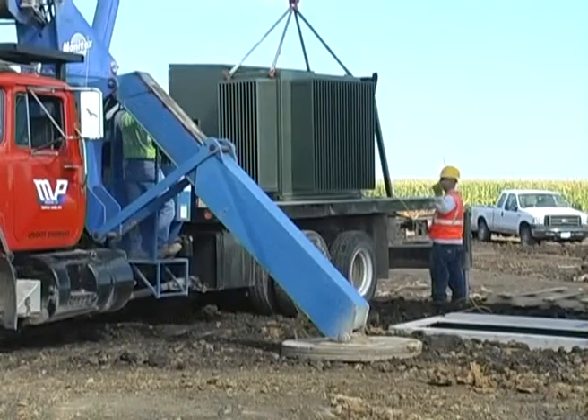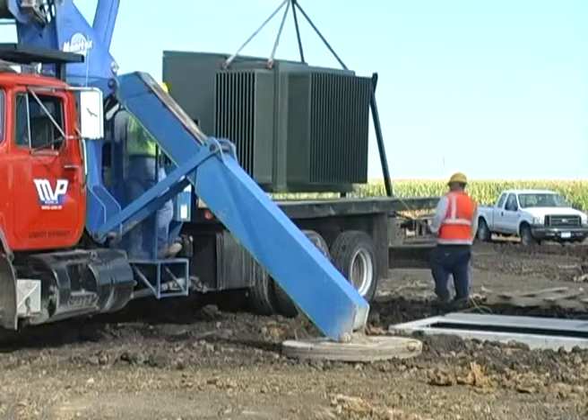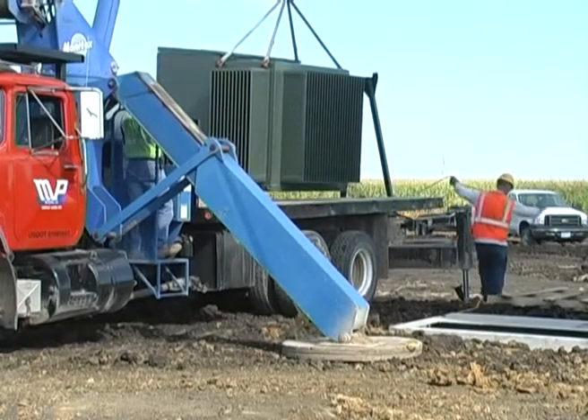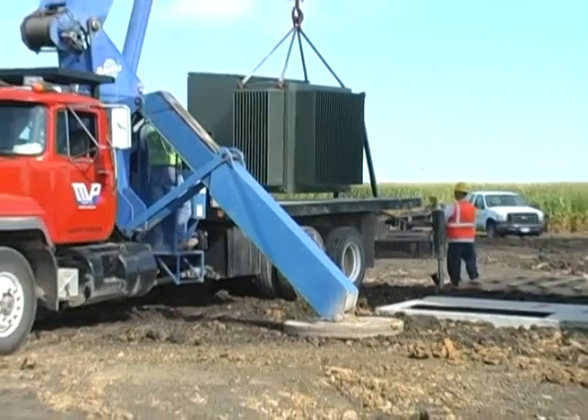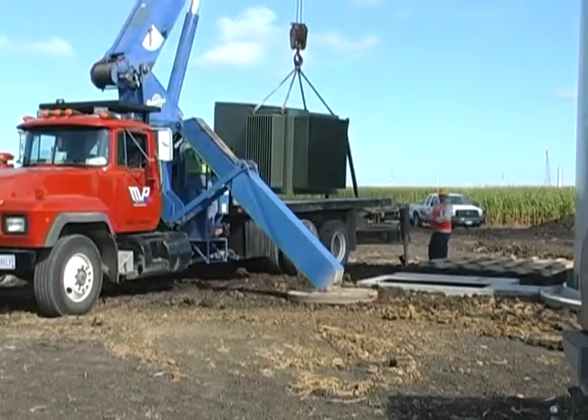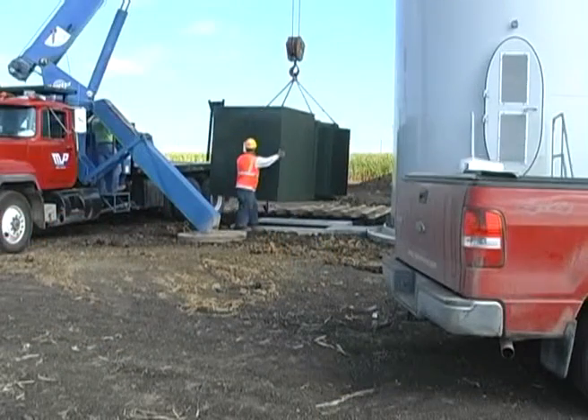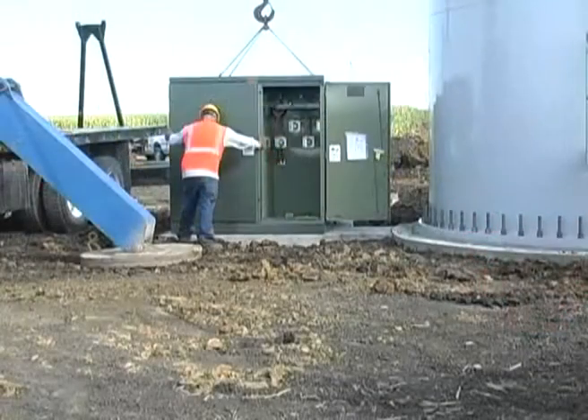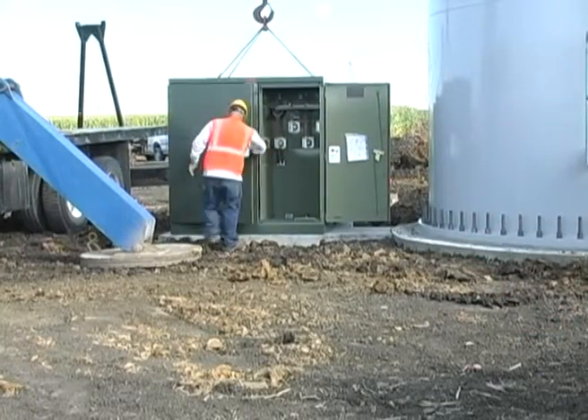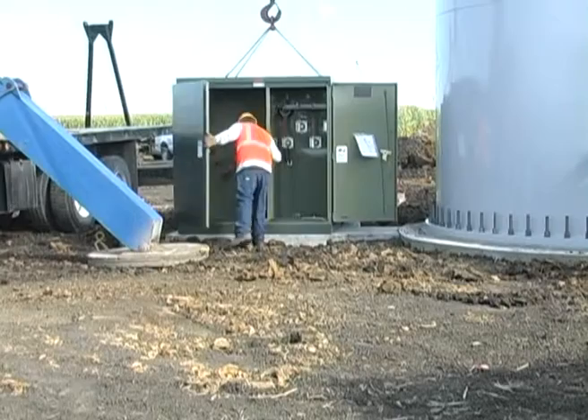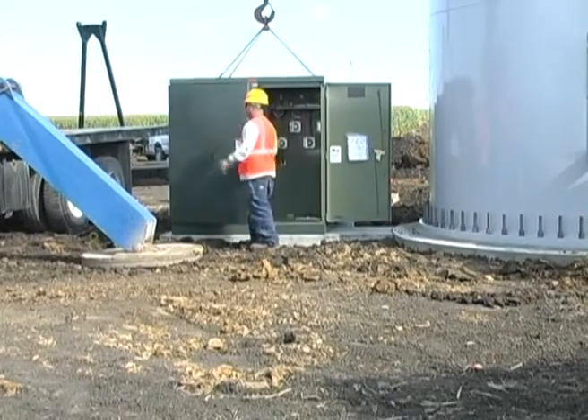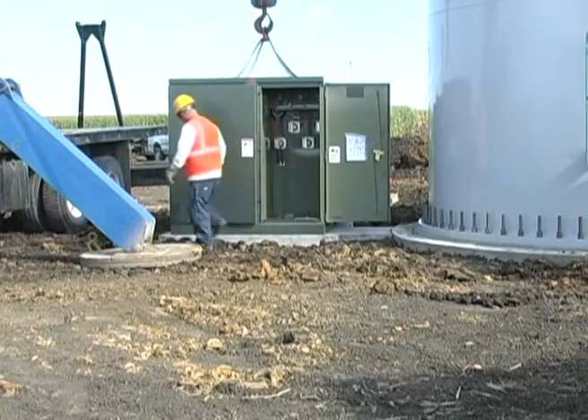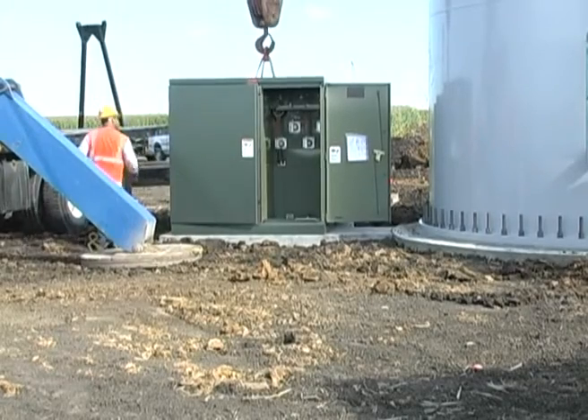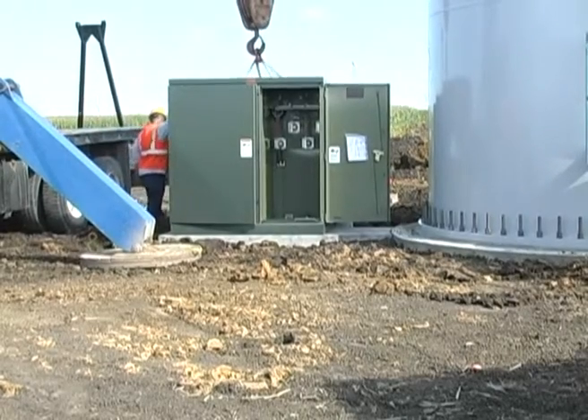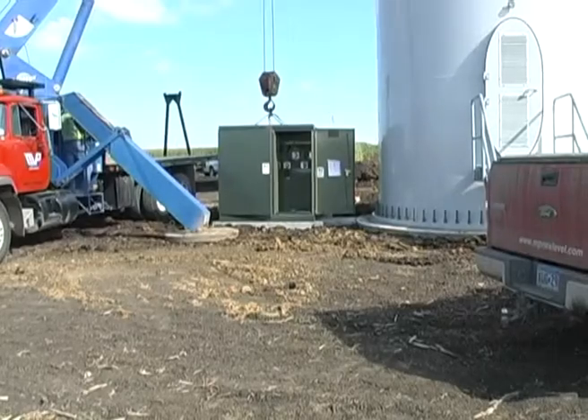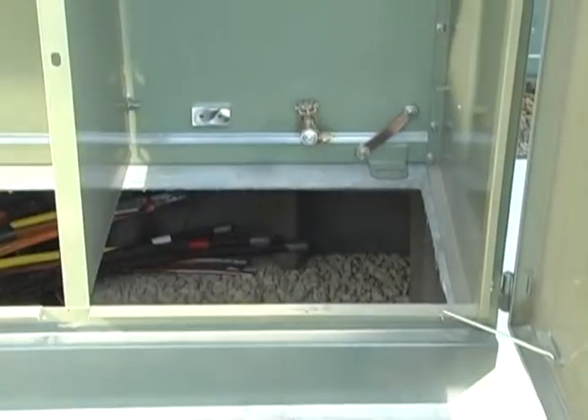The base is now ready to accept the installation of the transformer. A 2500 kVA 15,000 pound transformer is picked from the truck, gently guided, and set on the base. The openings in the top face of the box pad are coordinated with the transformer base dimensions to match up exactly. Transformer weights and footprints should be supplied with the request for quote so that Concast can provide the correct box pad with a perfect fit.